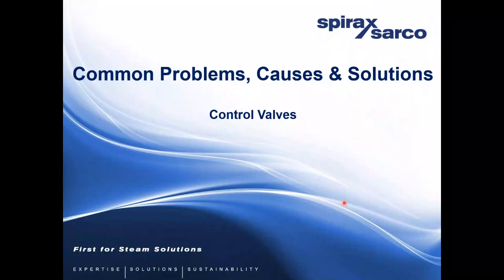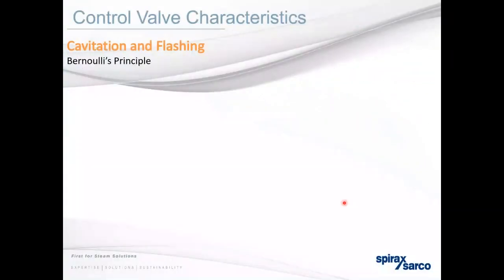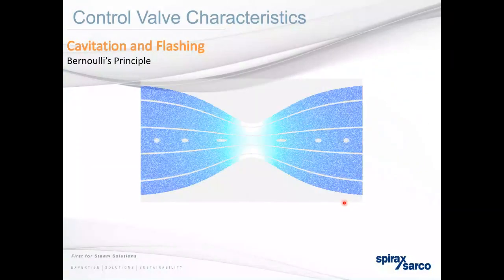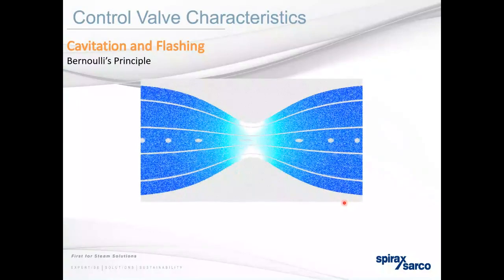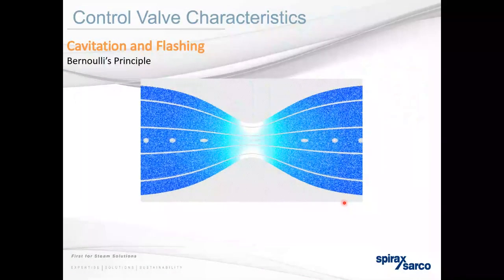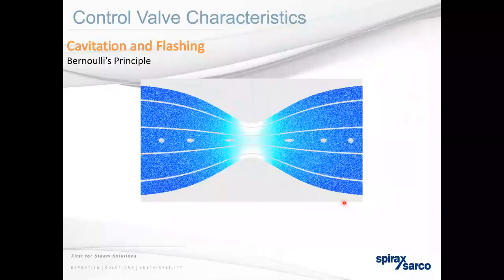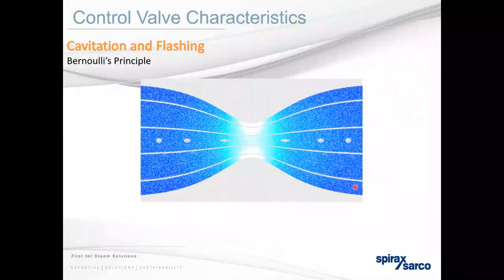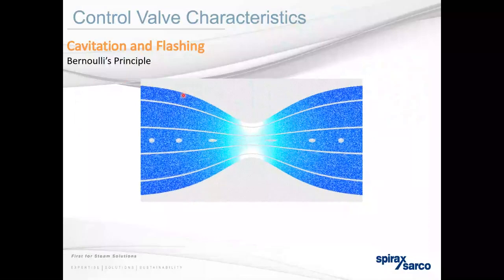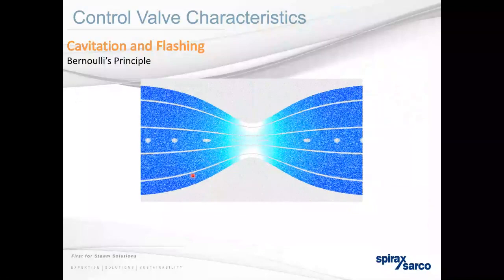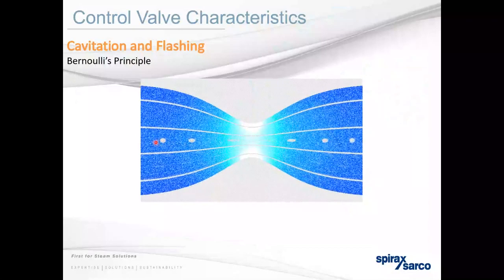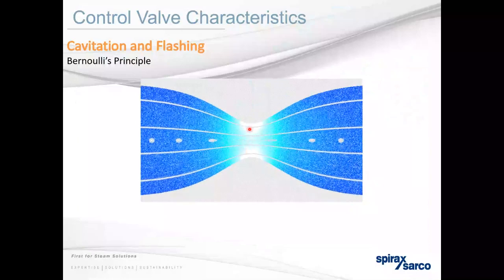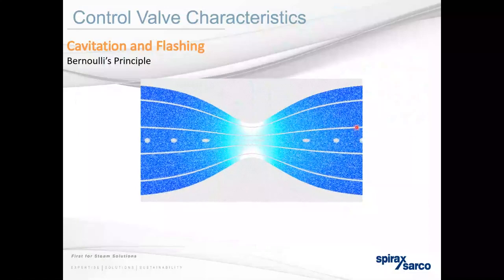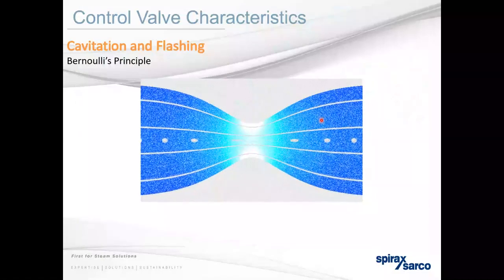So we now come to common problems, causes and solutions for control valves. So first, Bernoulli's principle. Bernoulli's principle effectively is fluid dynamics. It states that the increased speed of any fluid will decrease the pressure and decrease the fluid's potential energy. So as you can see here, if you imagine that this is a valve seat, as it comes through your pipe on your inlet, it then is reduced by the orifice of the control valve, leading it to speed up, which gives you a pressure drop. And then when you get to your outlet piping, it then returns to its normal flow.